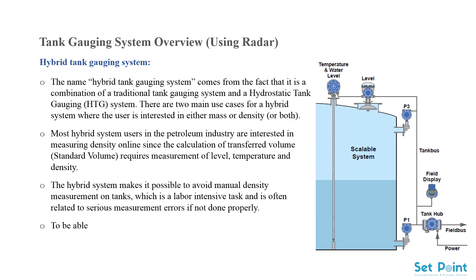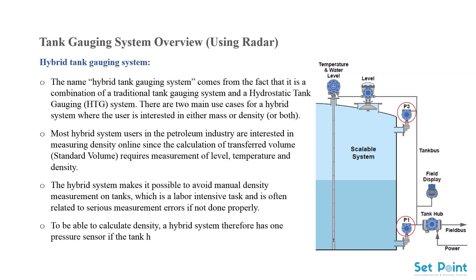To calculate density, a hybrid system uses one pressure sensor if the tank has atmospheric pressure, and two pressure sensors (P1 and P3) if the tank is not freely ventilated.